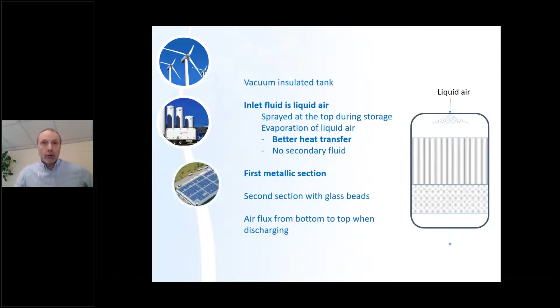So in the final demonstrator, using the knowledge we gained from the experiments, the prototype currently used in Frigologics is based on a vacuum insulated tank to drastically reduce thermal losses. The inlet fluid is now liquid air, sprayed at the top during storage. There is a first metallic section that evaporates the liquid air. The idea behind this is to have much better heat transfer due to evaporation heat transfer.